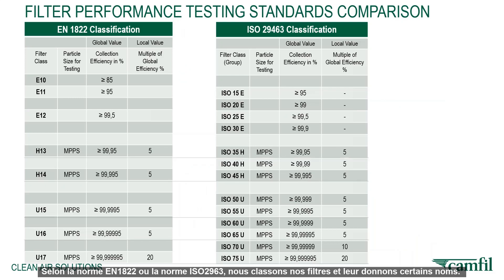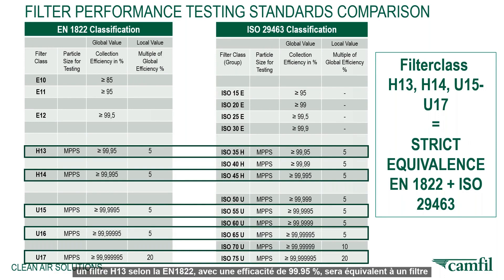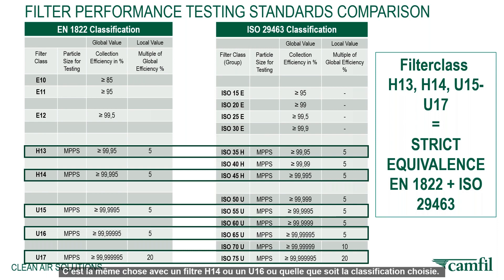According to EN1822 or ISO 29463, we classify our filters and give them certain names. Looking at the comparison, a H13 filter according to EN1822, which is 99.95% efficient, would be equivalent to an ISO 35H according to ISO 29463. These are both efficiencies at the MPPS. The same applies to H14, U16, or whatever classification you want to use.